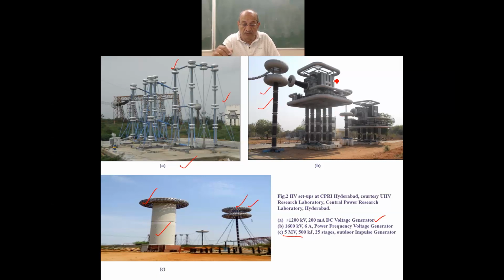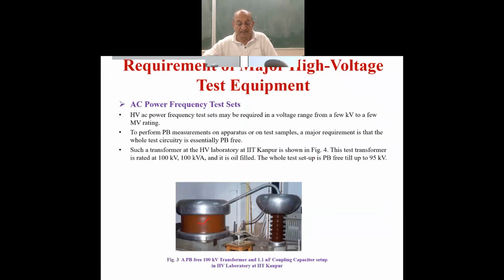This is also a tube electrode of very high diameter. It is all to increase the size of the conductor, the radius of the conductor, to the extent possible, in order to bring down the electric field density around it. That is one of the ways of stress control. So that makes the size of the equipment larger. And in this case also, pipes and a dome are used to make the whole setup PD free, but this is only up to 100 kV.